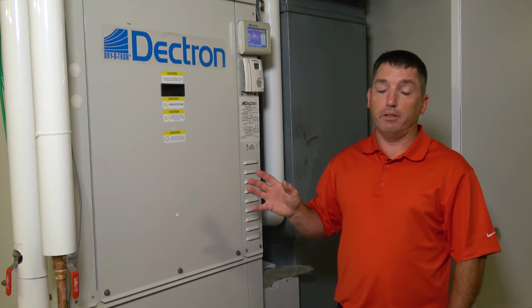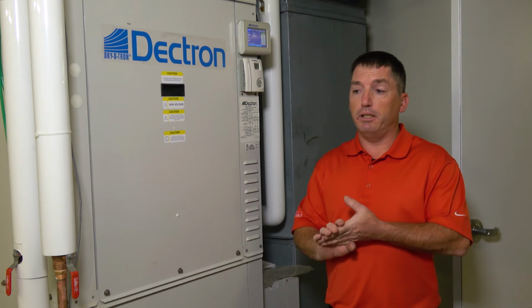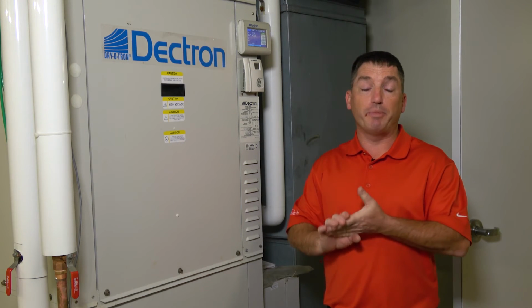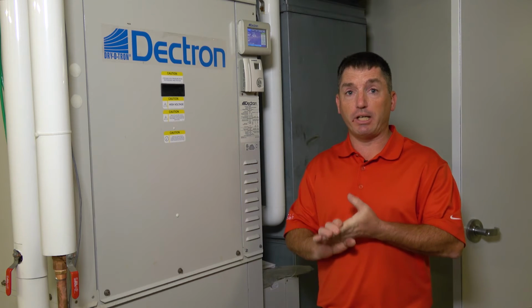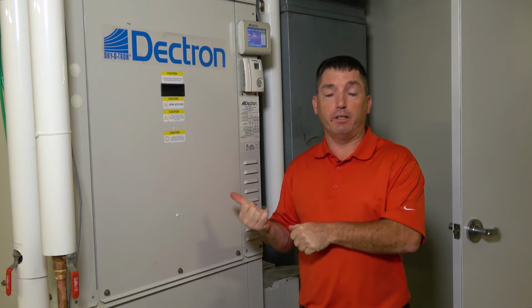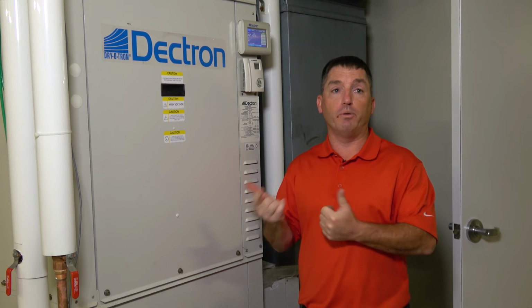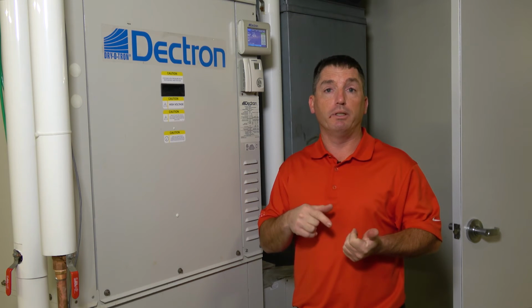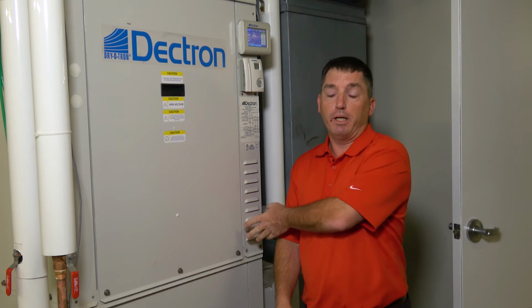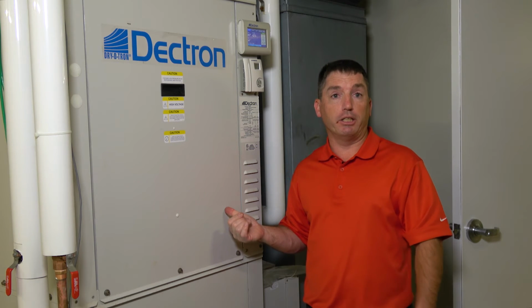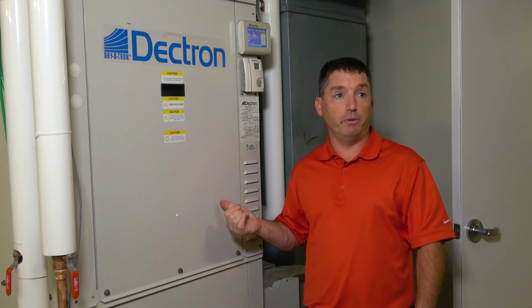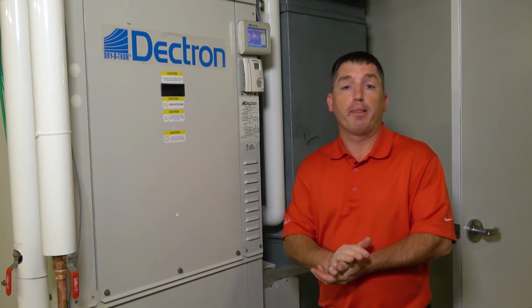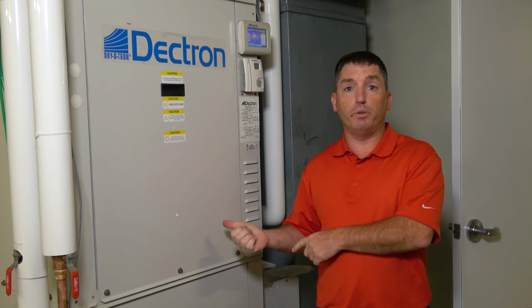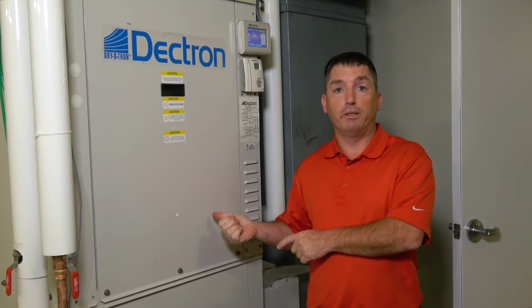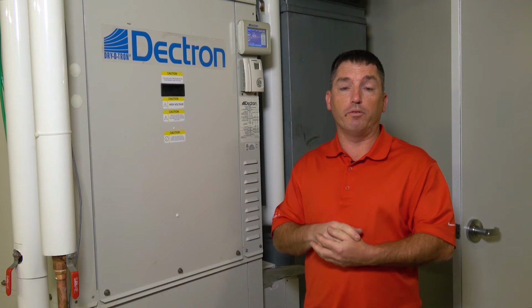The third option we have is if the space temperature is satisfied, we have the energy in the refrigeration circuit. We don't want to put it back into the air because we would overheat the room. We have a plate heat exchanger in here that is connected to the chilled water loop. That way we'll dump the heat to that, which will prevent overheating the space.